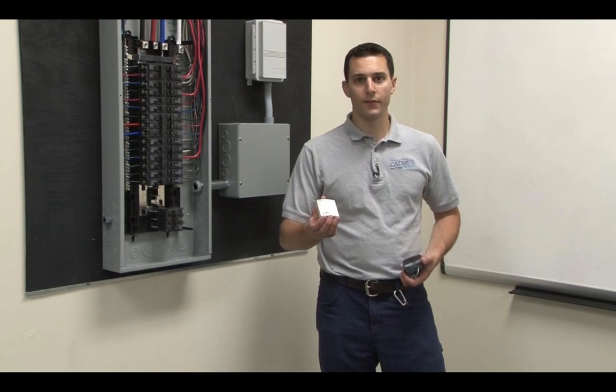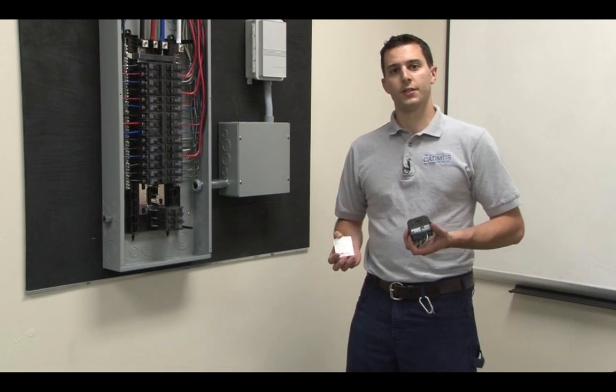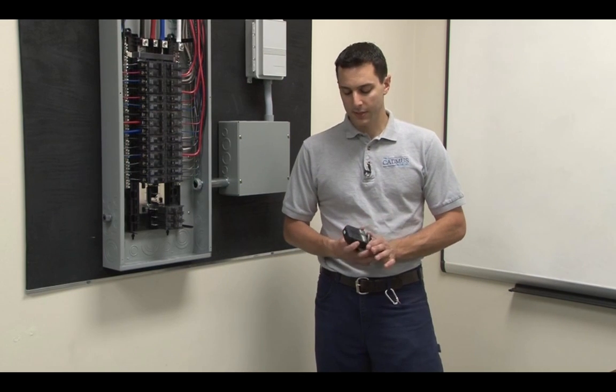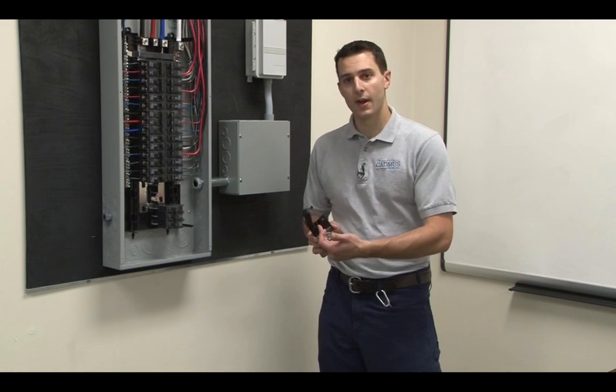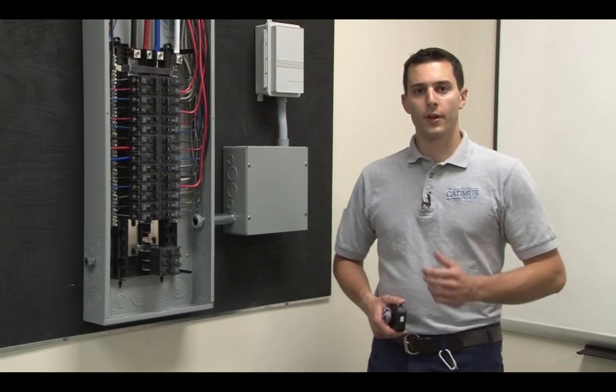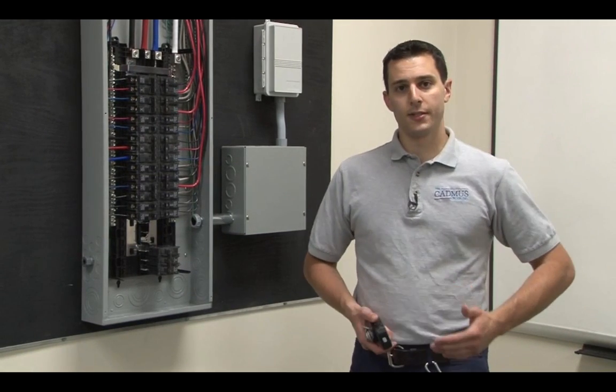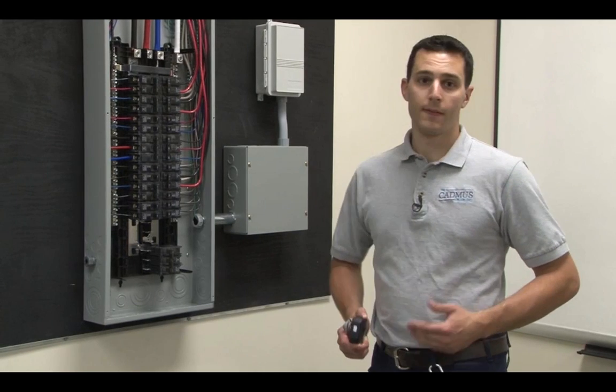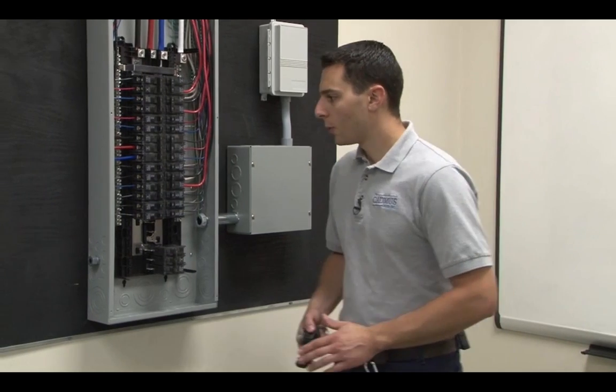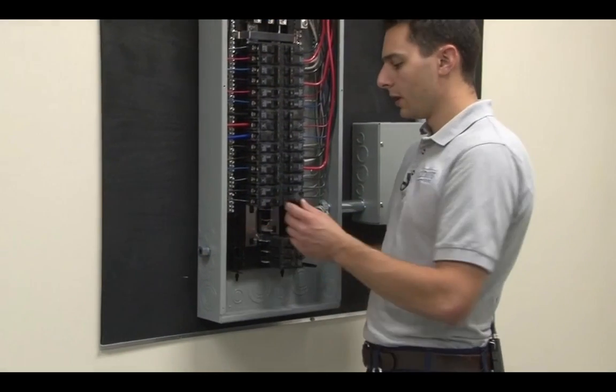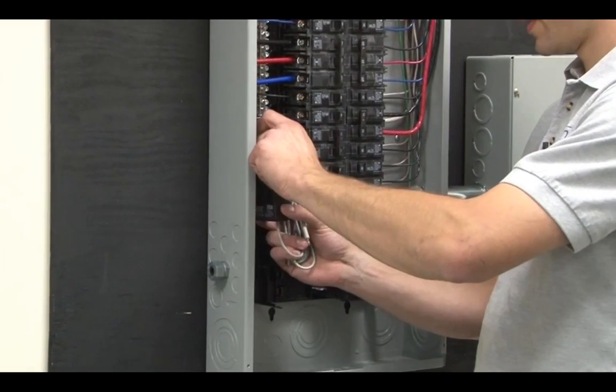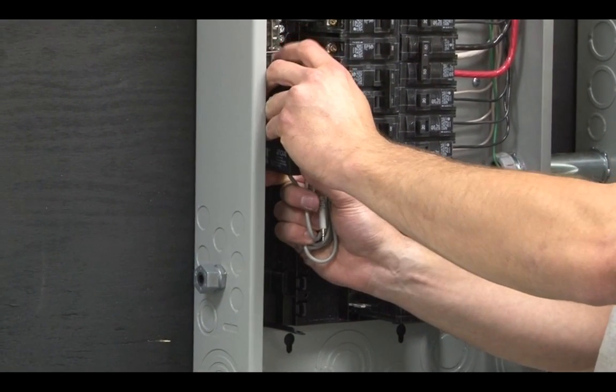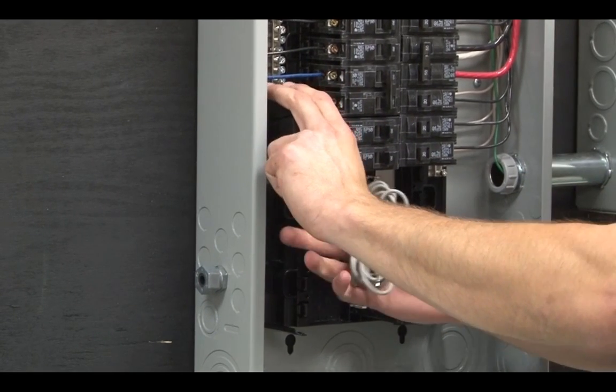We'll now install a data logger on a single circuit to monitor the amperage. We'll do so by using an Onset HOBO U12 data logger and a CTVA, which is a split-core current transformer. This particular current transformer is not directional, so it doesn't matter which end the wire goes in. We'll be working with our demonstration panel board, which is de-energized, so we can focus on the meter installation. If this were an energized panel board, I'd be wearing all the necessary safety gear to work in it.